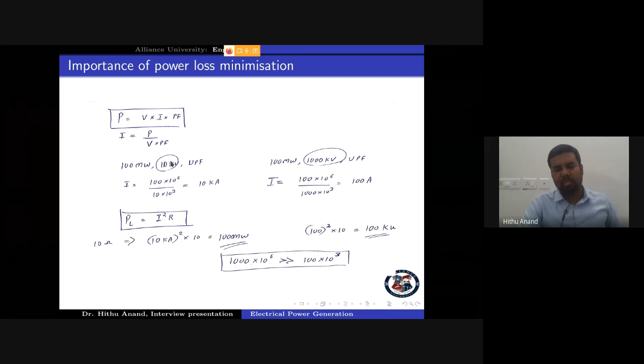So 1000 megawatts of loss is far greater than 100 kilowatts, which is why we step up the voltage. This is of course an arbitrary value just to explain the concept, but it shows why we step up voltage from 11 kV to 400 kV in transmission - to minimize power losses. We have much less power loss compared to transmitting at lower voltages, and that is the main reason we step up the voltage.